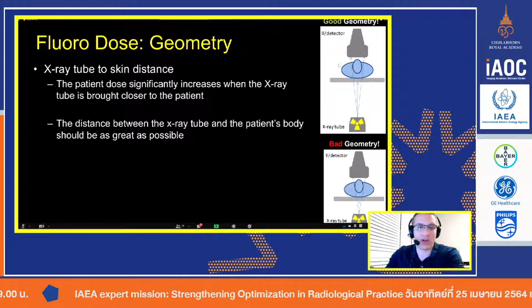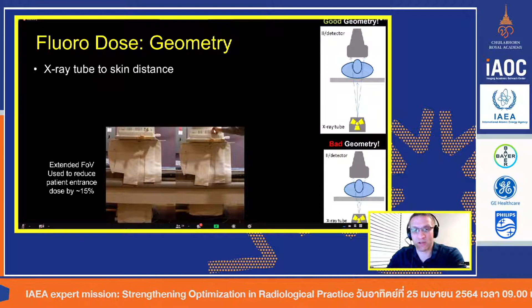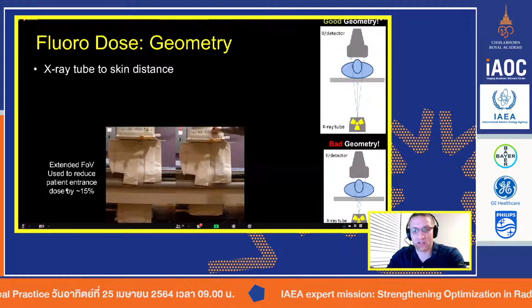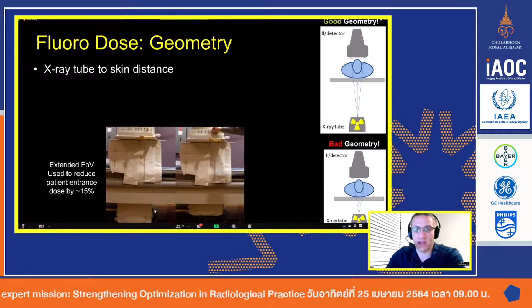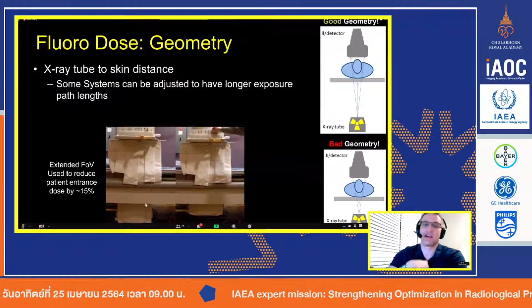So on these tilt tables, one vendor that I know of, maybe other vendors can do this, but one vendor has a button you can push, and it will make the X-ray tube go farther away. It goes from its normal position to down a little farther. If you do this, and this is how we use our machine at our center, because this is actually a picture at my hospital, it immediately reduces the dose of the patient by 15%, just because it extended the distance. Now, they built this actually to make a larger field of view. So if you had a big patient, the only reason they did that is so that you could actually image a little bit more anatomy. What they didn't realize was we would use it, as most people use it now, for dose reduction.